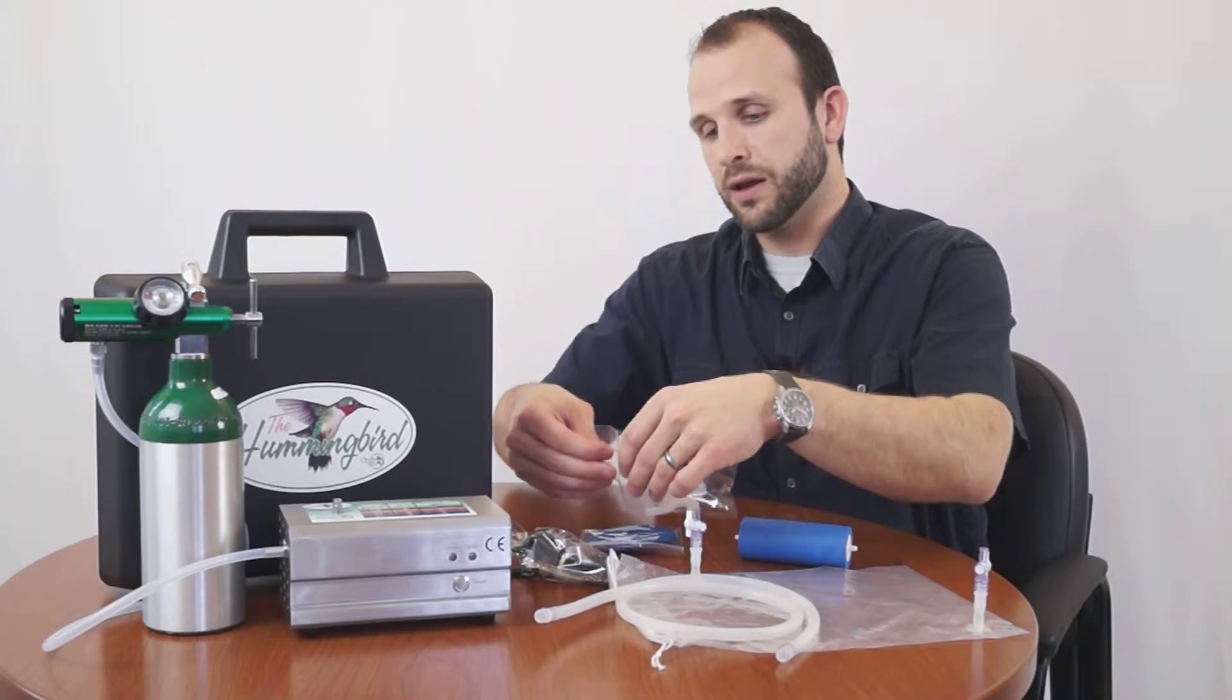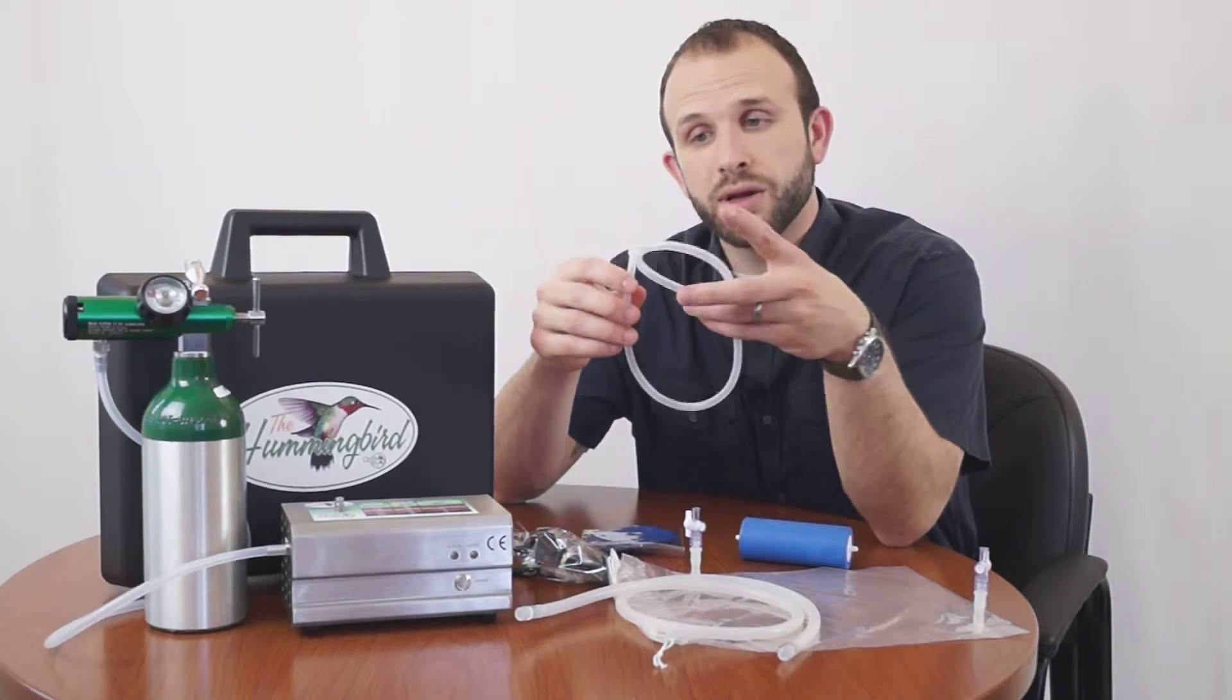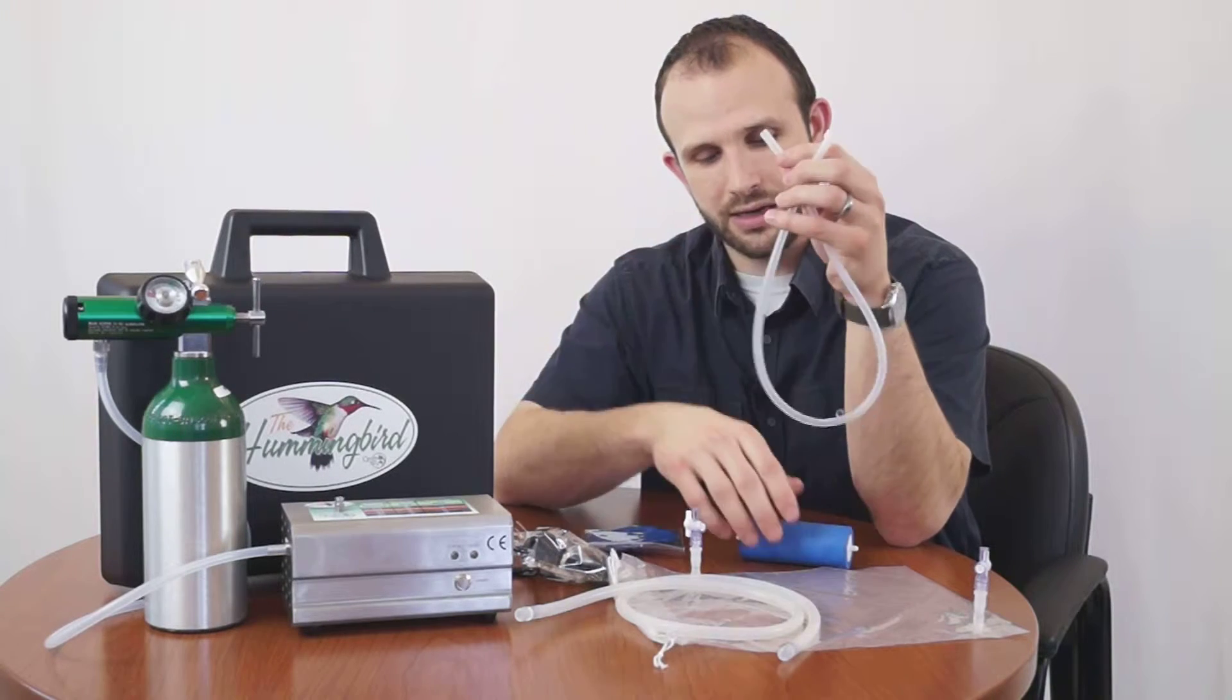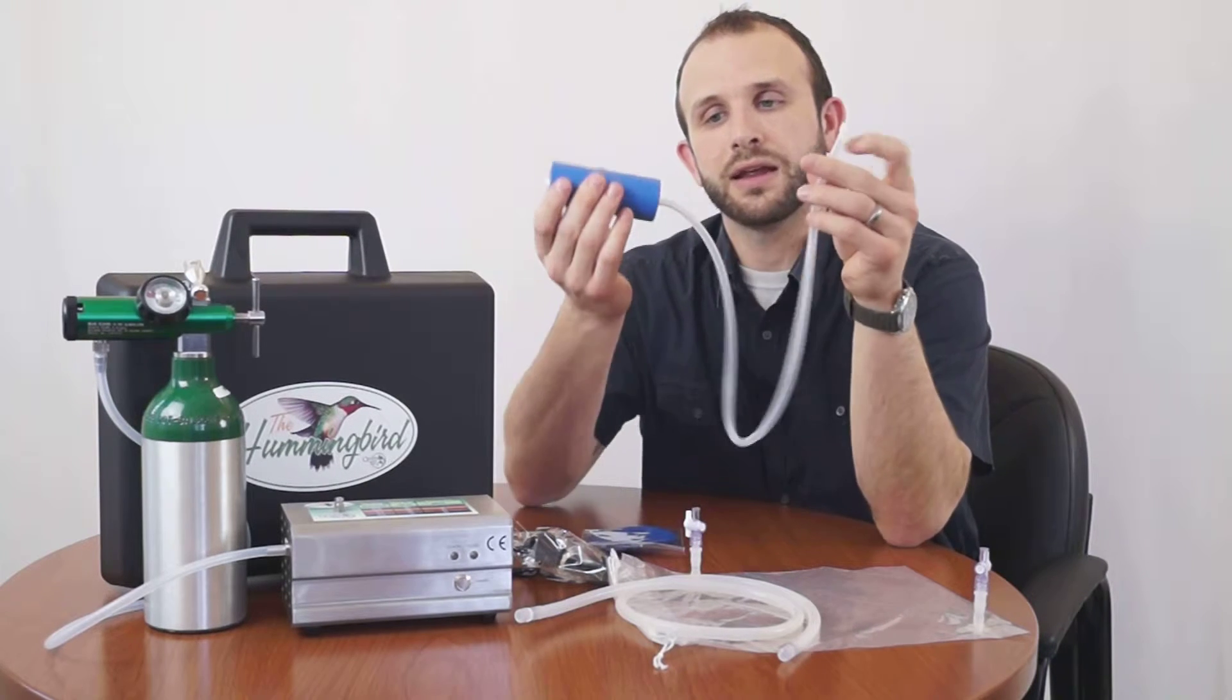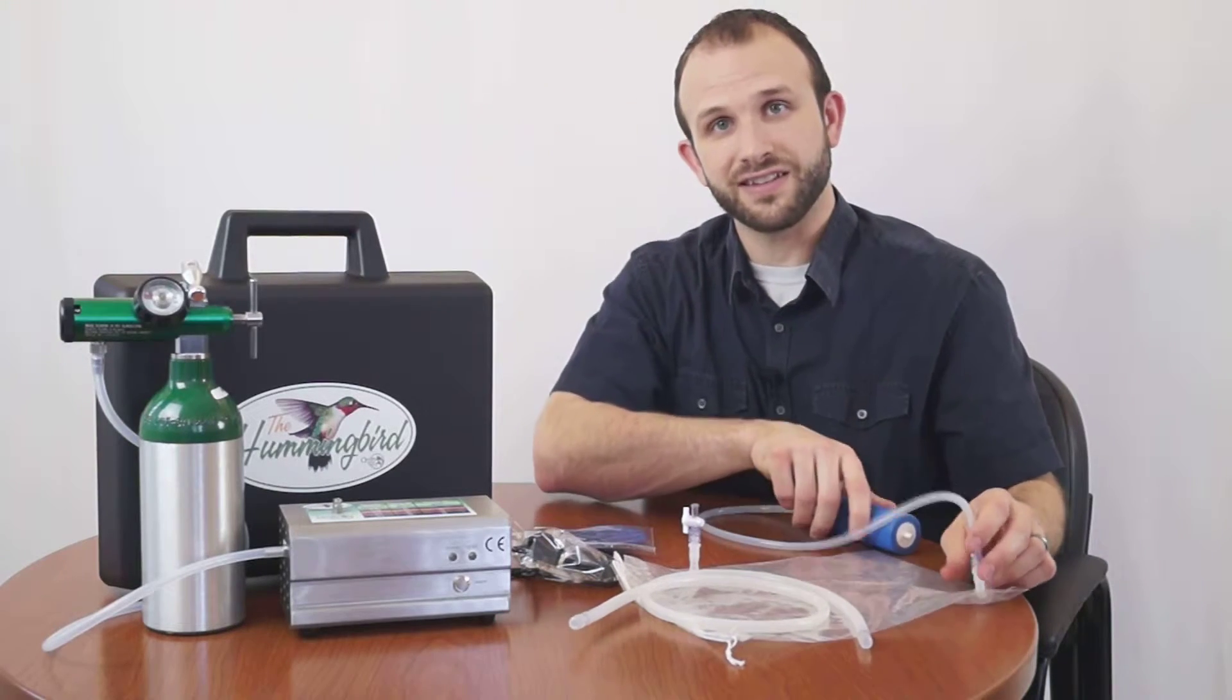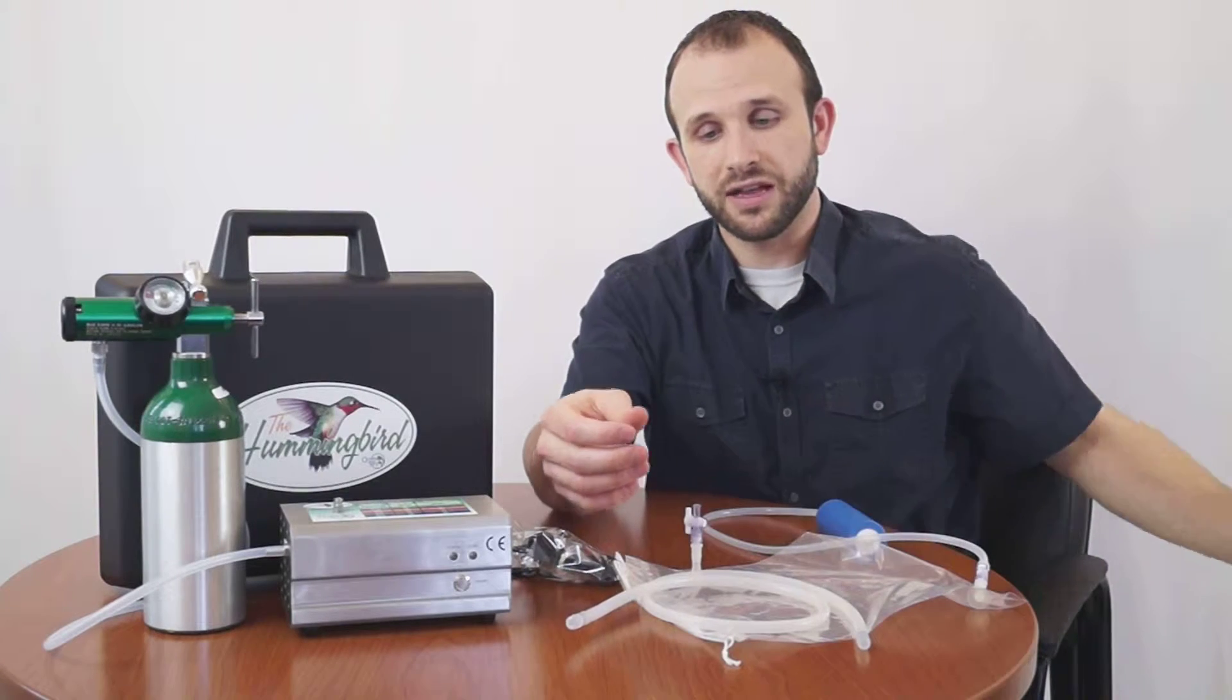The next tube that we have here is actually the tube that's going to run from our bag to the destruct. This tube will be connected to the destruct on one side and to the bag on the other side. We'll just go ahead and connect that up right now. We'll take our destruct, insert that onto the tube, and we can actually connect that directly to our bag. There we go. Now our destruct is connected and ready to capture any of that unwanted ozone or get rid of the ozone once our procedure's done.